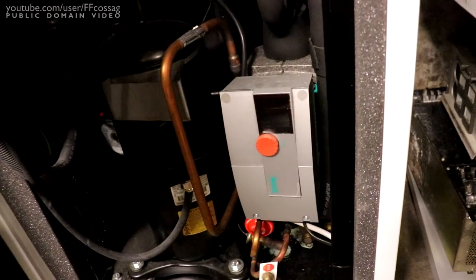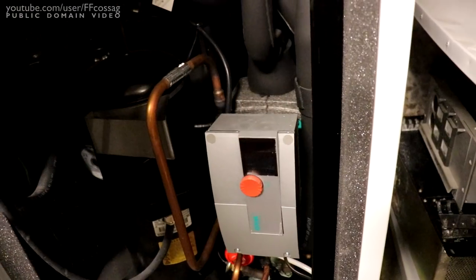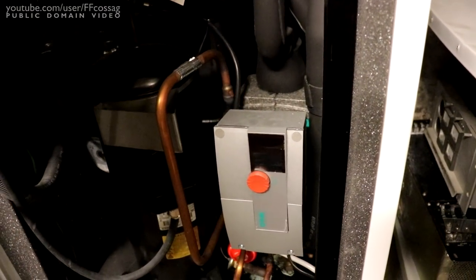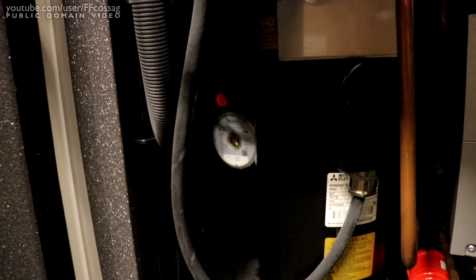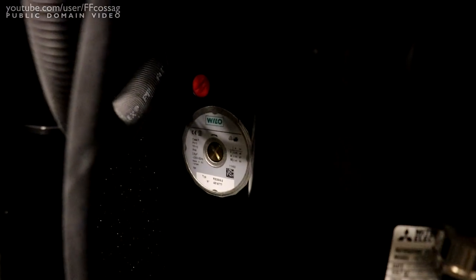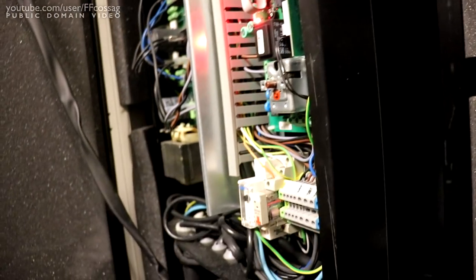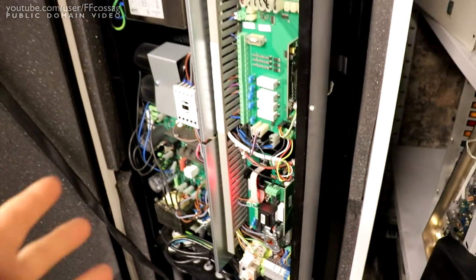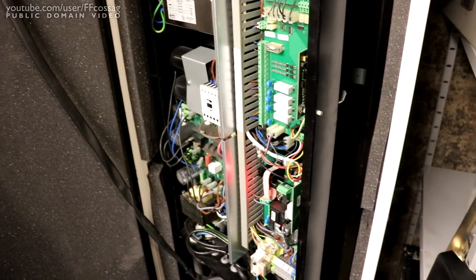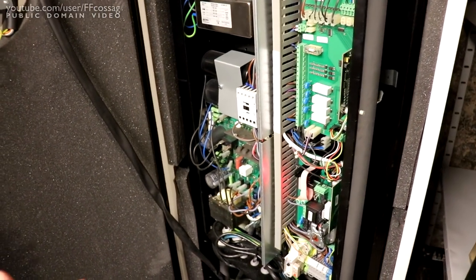So if you're unfamiliar with ground effect heat pumps, you have two circulation pumps - one big one for the ground effect heat exchange that's pumping liquid out to a huge tube in the ground, and one circulation pump in the back for the radiating, providing circulation to the inside of the house. Thankfully this thing is equipped with an emergency mode so I just got up and flicked the switch and now it's just running everything on pure electric but that's incredibly inefficient. Instead of drawing five kilowatts sometimes this thing's drawing six and a half kilowatts continuously which is just incredibly expensive to run.